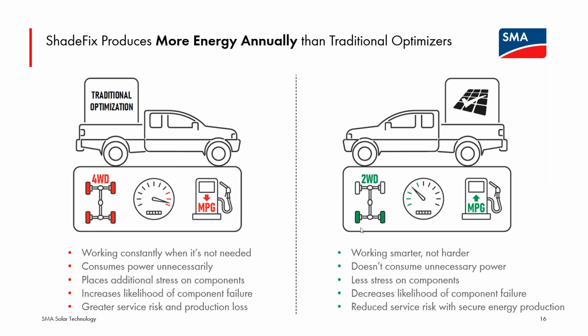And also, having as much functionality left in the inverter as possible reduces complexity out at the array. Having DC optimizers touching each and every module that have to have circuitry to be able to boost or buck voltage, and that will be utilizing that circuitry all of the time the system's in operation, means that there's a far more complex system, and those power conversion devices are in the harshest environment of the system and the hardest to access should something go wrong.